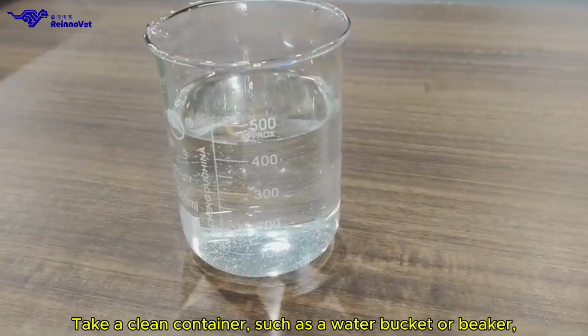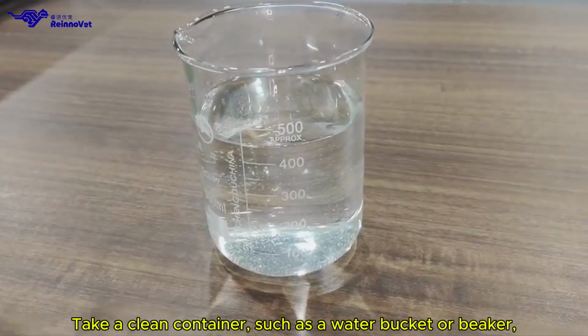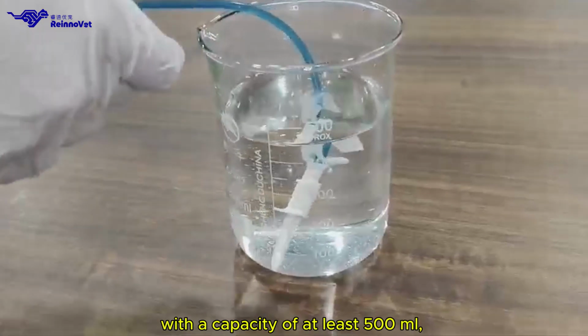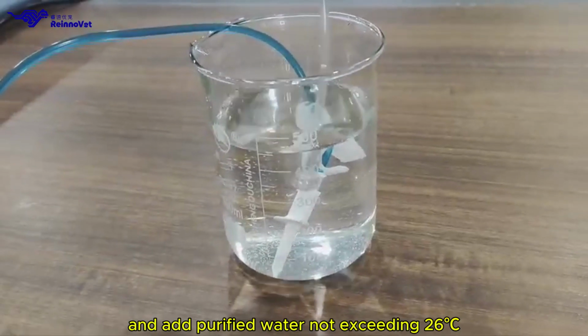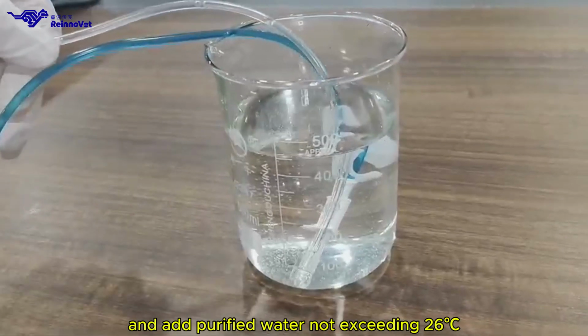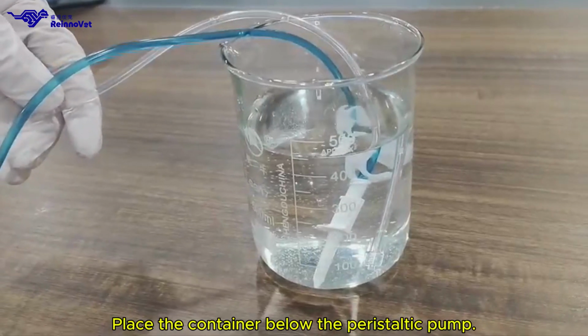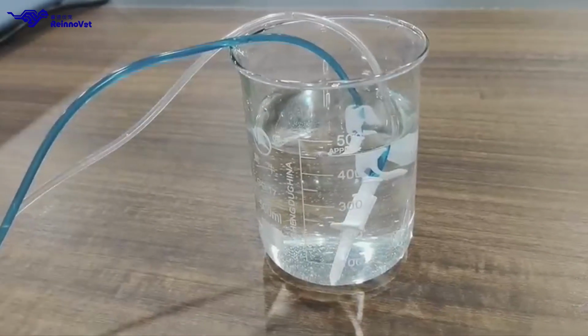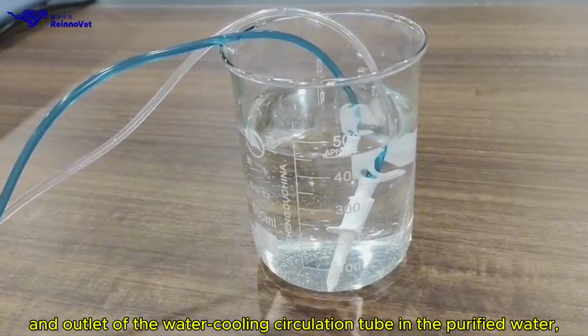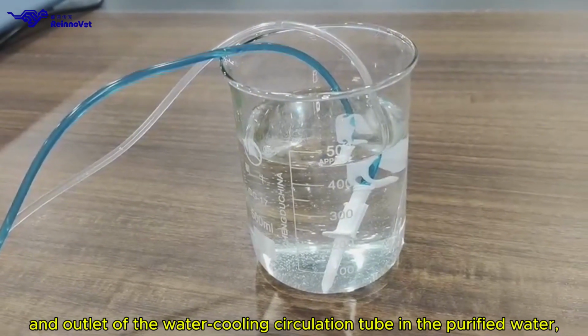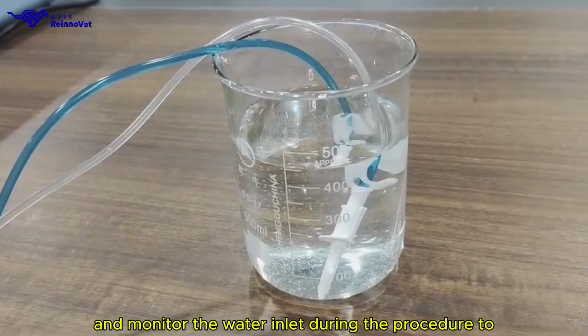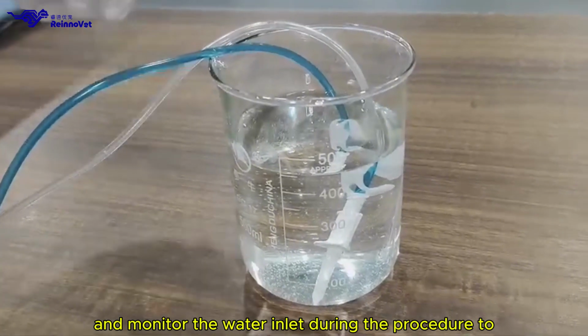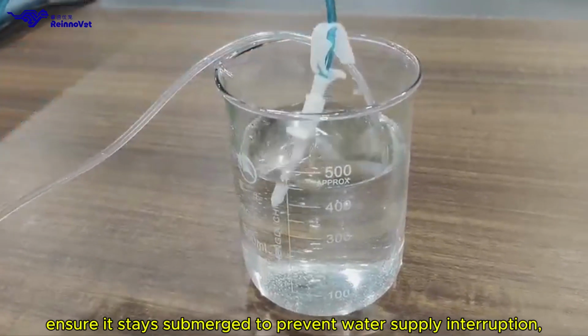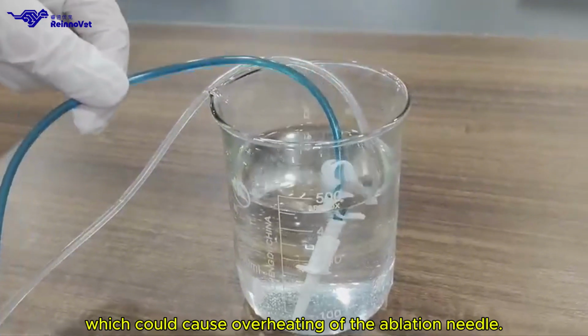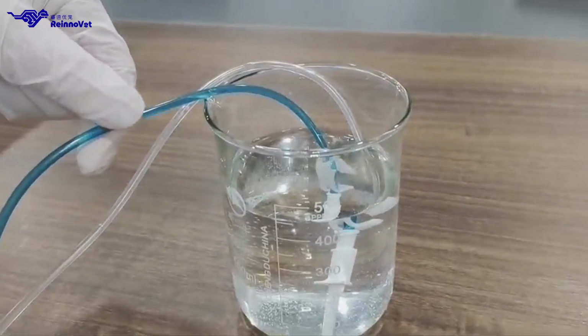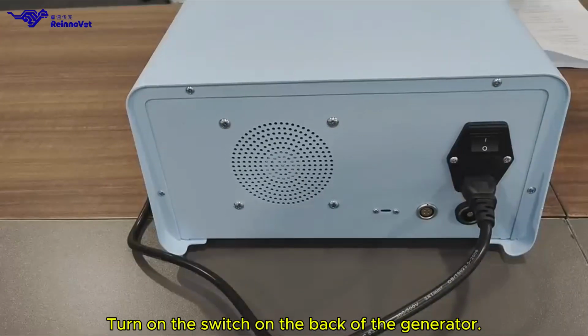Take a clean container, such as a water bucket or beaker, with a capacity of at least 500 milliliters, and add purified water not exceeding 26 degrees centigrade. Place the container below the peristaltic pump. Submerge both the inlet and outlet of the water cooling circulation tube in the purified water and monitor the water inlet during the procedure to ensure it stays submerged to prevent water supply interruption, which could cause overheating of the ablation needle.